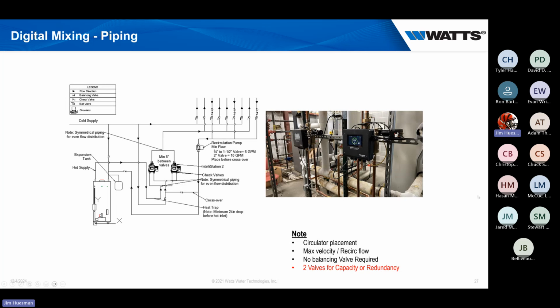If I come over to my spec sheet to design this, I always start off with a 10 PSI drop. At a 10 PSI drop, this small 1-inch valve is able to do roughly 73 gallons a minute. Now if I take 73 times two, that's 146, and now we're over top of what we need.